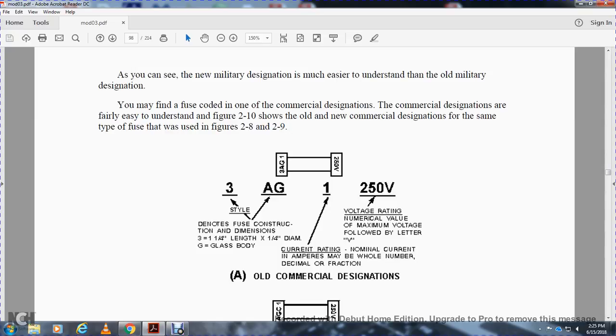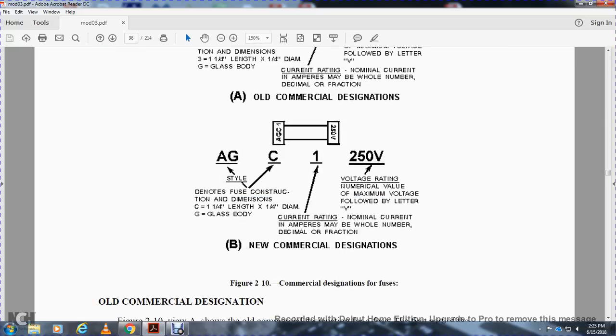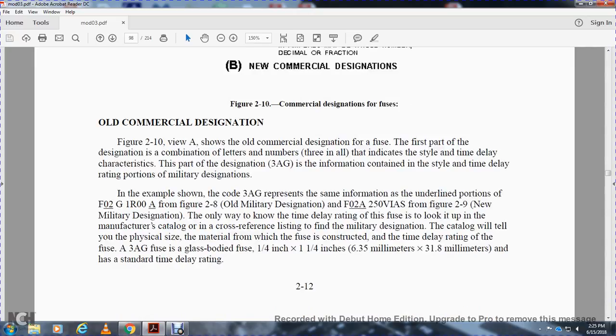Commercial designation: the commercial designation is fairly easy to understand. Figure 2-10 shows the old and new commercial designations for the same type of fuse used in Figures 2-8 and 2-9. In the old commercial designation, '3AG' would denote the fuse construction dimension - one and one-quarter inch length, one-quarter inch diameter, glass body. The current rating is the nominal current in amperes and may be a whole number, decimal, or fraction. The voltage rating follows. In the new commercial designation, 'AGC' denotes the style, construction, and dimensions - one and one-quarter inch length, one-quarter inch diameter. 'G' stands for glass body. In the old commercial designation shown in Figure 2-10, the designation is a combination of letters and numbers. For example, '3AG' contains information including the time-delay rating, similar to the portion of the military designation.